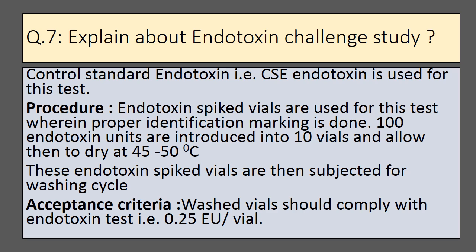The next important question is: explain the endotoxin challenge study done for the vial washing machine. Control standard endotoxin (CSE) is used for this test. In the procedure, endotoxin-spiked vials are used wherein proper identification marking is done prior to washing. 100 endotoxin units are introduced into 10 vials, and these vials are allowed to dry at 45 to 50°C. These endotoxin-spiked vials are then subjected to the washing cycle. Acceptance criteria: after washing, vials should comply with the endotoxin test limit of 0.25 EU per vial.